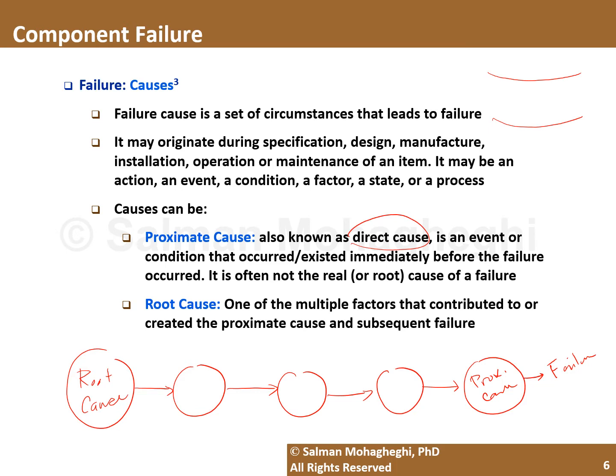However, the proximate cause of the failure could be, for instance, that one of the phases, for example, this phase, gets closer to the other phase, violating the safety clearances. Now, this is the proximate cause, the immediate cause that led to that failure of short circuit. But what are the root causes for this? The root causes could be different things. For example, this could happen due to conductor galloping, which could be as a result of high winds blowing in that area. Or, for example, this particular phase, let's call it phase A, might be overloaded, meaning that the additional thermal energy due to ohmic losses would lead to the additional sag of the conductor. Hence, this particular phase will get closer to phase B, leading to that short circuit.